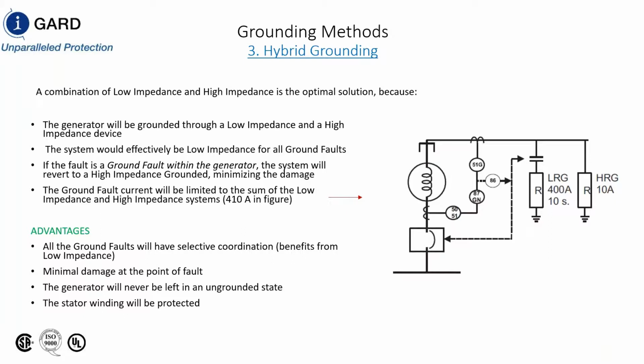Okay, excellent. Next question. Do you have any guidelines for sizing a bus zigzag resistor, say 200 amps versus 400 amps? Are there any high-level estimation methods to size these based on the system? Again, the low resistance ground system is going to be sized so that the minimum ground fault pickup selects the size of the ground fault resistor and the zigzag. I have no preference. There's no real cost differential between a 200 amp or a 400 amp 10-second resistor. Little bit of a size difference, but there isn't that much of a cost differential. So what determines a 200 amp versus a 400 amp is whether you can detect a 200 amp ground fault.